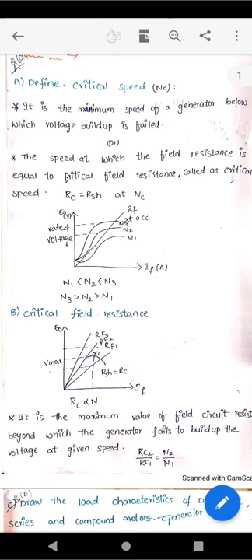Critical field resistance is the maximum value of field circuit resistance beyond which the generator fails to build up voltage at a given speed.